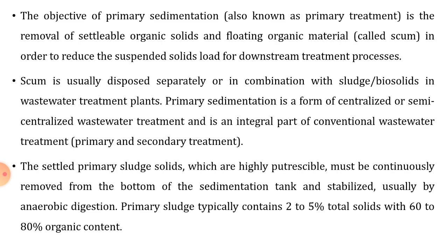The objective of the primary sedimentation is the removal of settleable organic solids and the floating organic material called scum in order to reduce the suspended solid load for downstream treatment processes. So it is very much essential that whatever settleable organic solids and floating organic material in the form of scum should be removed before the secondary treatment, because it will unnecessarily increase the load on the treatment unit. Scum is usually disposed separately or in combination with the sludge or the biosolids in the wastewater treatment plant.